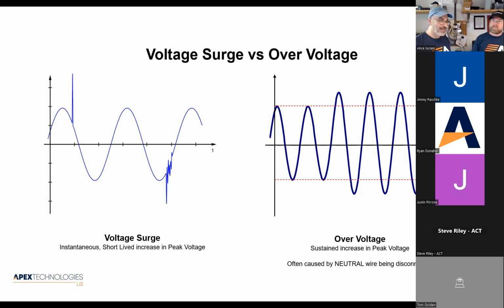The power company does a great job when they're generating whatever voltage their target is. They've got pretty much control on there. But once it starts going through these transformers, if the transformer connections get loose, sometimes it can cause a change in these voltage levels. A lot of times it goes over voltage, and you have an over voltage condition, and the remedy is an electrician needs to come out and tighten up a wire, which means it's sustained for a very, very long period of time, right? So that's definitely an issue.